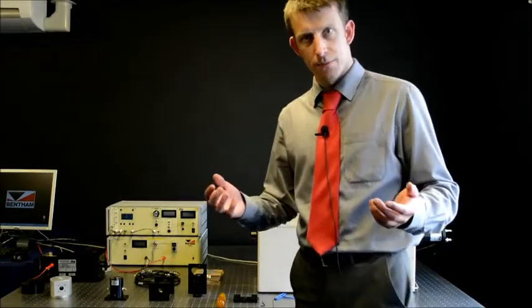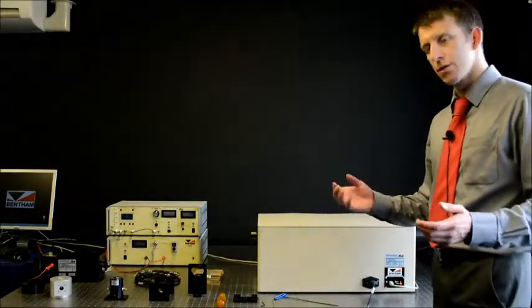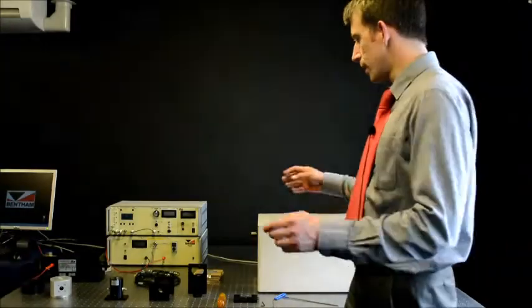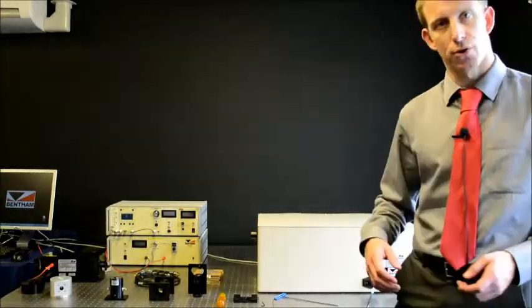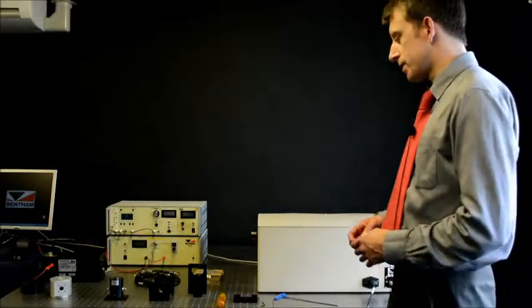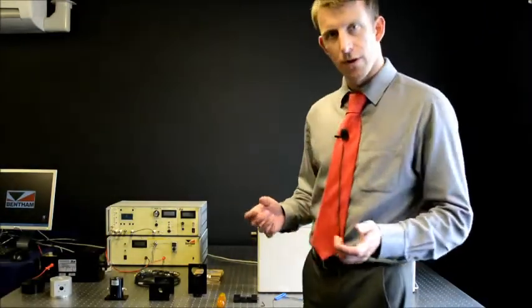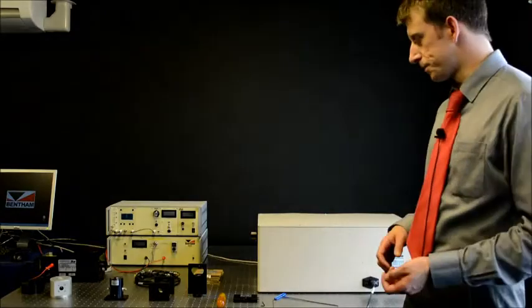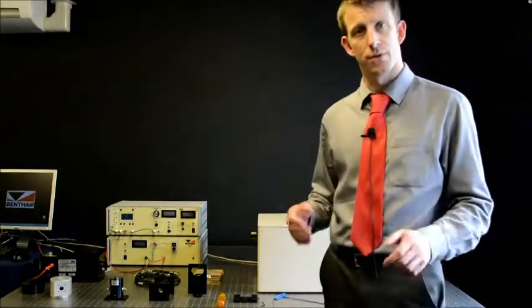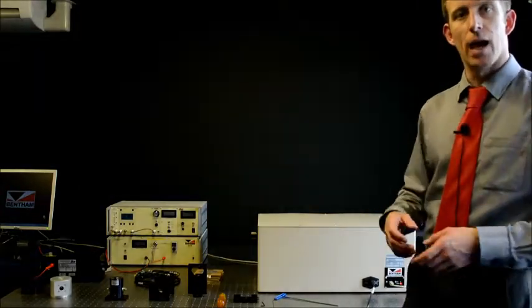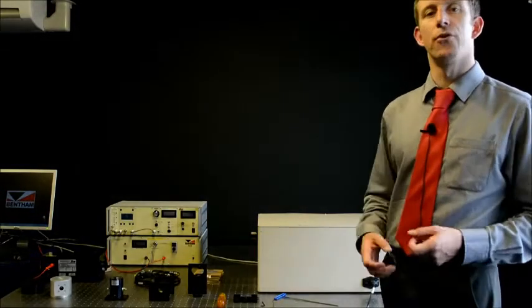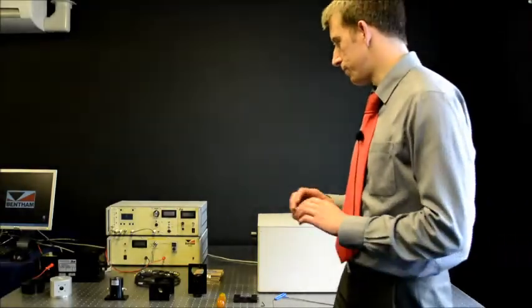Infrared is heat. The signal from the source may be confused with that of heat emitted from the background, the structure of the monochromator, etc. It is for this reason that we, in infrared, must optically chop the signal. Optically chopping the signal is effectively modulating the signal on a known carrier wave and effectively seeking that signal in the detection electronics and ignoring any DC base level.